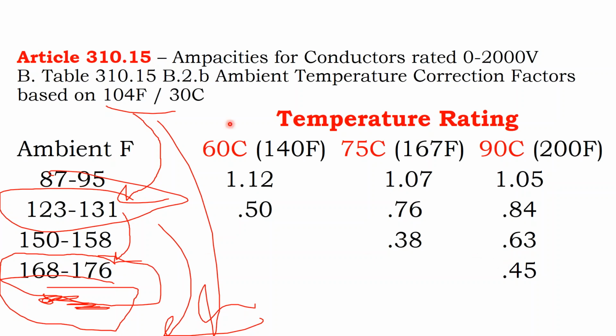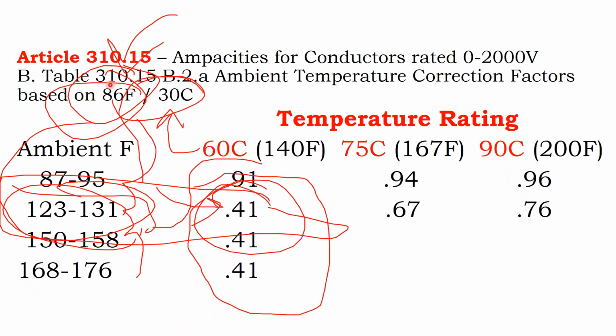It doesn't even give me a 60C or 75C option. It says, look, you're beyond the temperature rating of this cable, so you should not be using it on the rooftop. Even though you're using a 200 degree rated cable, you need to reduce the ampacity of it by 55% in order to adjust for the fact that the cable is already hot up on the rooftop. And then you'd use a different table that doesn't show the correction factor, but shows the actual amperage rating. And you'd make sure that you're using the 140 degree table as opposed to the 86 degree table.